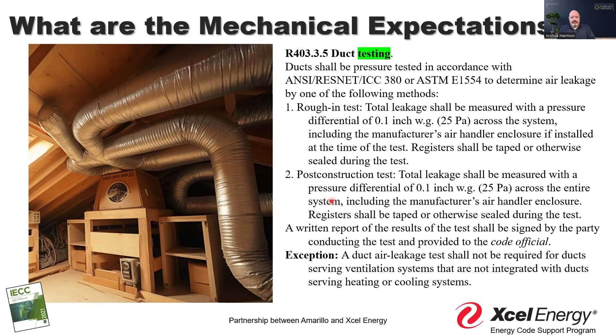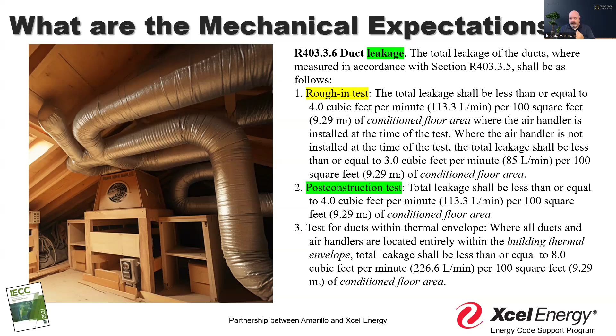I've seen tests that come back with no leakage because they've taken the time to install it properly. They've thought about where it would go, so there are no pinch points and no tears from some other feature being put on top or ripping through it. Especially with flex duct, I see rips and tears in the lining all the time, leading to a bit of air loss. Depending on its location, that air loss can lead to moisture accumulation, condensation, and other bad things. These are things we consider in energy code compliance, reinforcing what we expect to see in buildings.